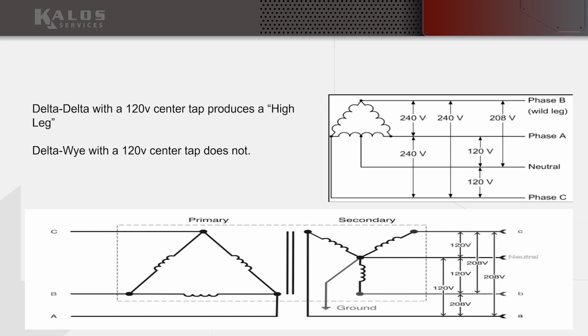that one of the key differences is if you did have a delta system and there was a neutral pulled off of that system, which in this illustration, you can see that the center tap of this coil is derived. That's called deriving a neutral, which just means grabbing the center of a coil. Is that you can get 120 volts, but you'll get what's called a wild leg or high leg, which by convention is typically going to be your neutral to B phase. By code, that's what we're looking for, although it could be any phase that is not the phase that you have derived your neutral from. So we can get into that in more detail once we get into more wiring details. But in the Y configuration, you won't have that wild leg or high leg. It's going to be an equal split of voltage on your three-phase.